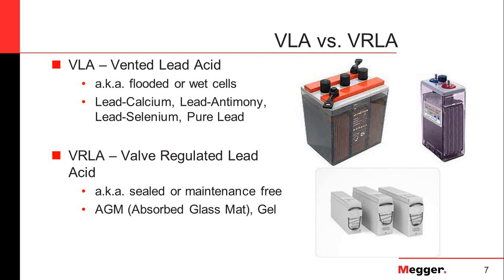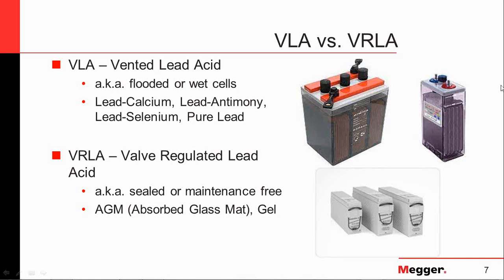The VLA is a vented lead acid battery. The VRLA is a valve-regulated lead acid battery. Vented lead acids are also called flooded cells or wet cells. You can always tell the difference because they will have a tank or jar where you can actually see through it. The valve-regulated are also called sealed or maintenance-free, though they are not truly sealed and not truly maintenance-free. They're containers you won't be able to see through to see the plates. Both are going to be some sort of lead alloy base or pure lead. Flooded cells have liquid electrolyte, while valve-regulated use absorbed glass mat or a gel cell.